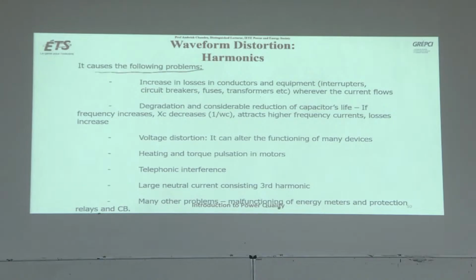Harmonics may cause the following problem: increased losses in conductors and equipment, fuses, transformers, wherever the current flows. Why will the losses increase? The first thing is the ohmic losses. And then perhaps you might have studied the skin effect. Suppose this is the conductor. If the frequency increases, the current will remain near the surface of the conductor. This is what is called skin effect. Because of that, the resistance increases, so losses will increase.